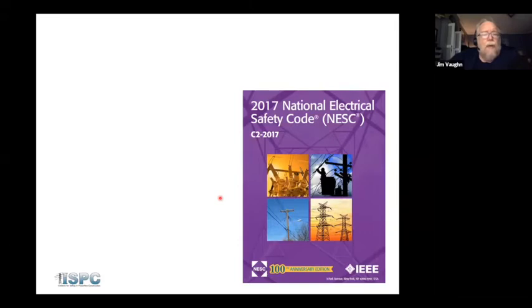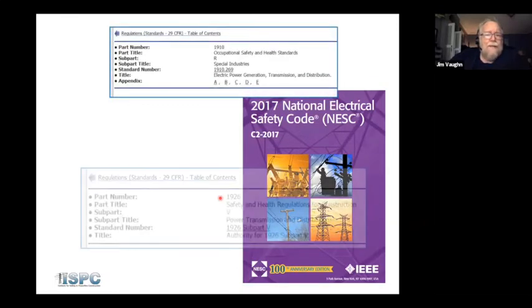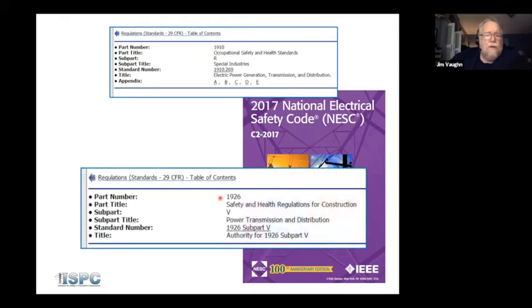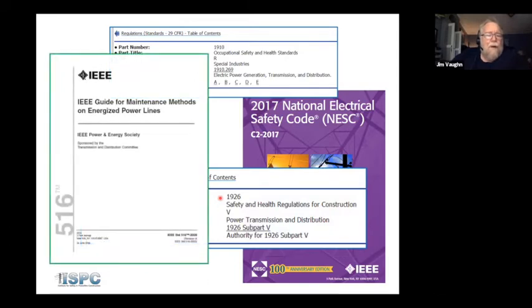Now, the MAD rules that we work by are regulated by the two OSHA standards, which are the 1910 standards for maintenance and operations and the 1926 standards for construction, the National Electrical Safety Code, and in particular, IEEE 516, which is the Guide for Maintenance Methods on Energized Lines. Now, here's what's important. OSHA standards tell us what we must accomplish, but they don't tell us how to do it. Your manual on how to do it, the recommendations on best practices, are these consensus standards. So if you are a safety person developing rules for operation of your system, you want to get copies of these consensus standards that apply, read them, and use them to judge or audit your procedures and to help you understand what you must do to keep your workers safe. That's the value of these consensus standards, and I can't emphasize that enough.